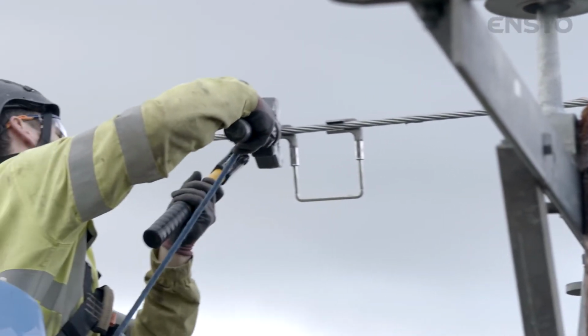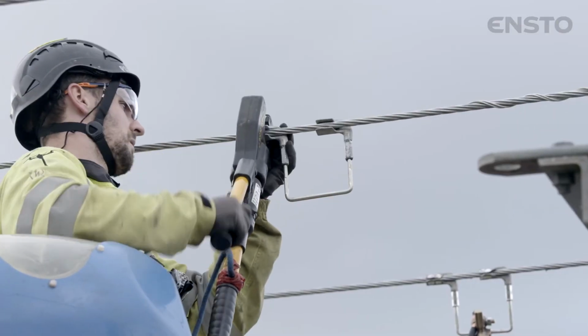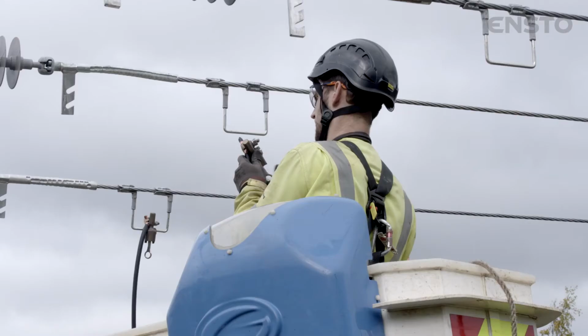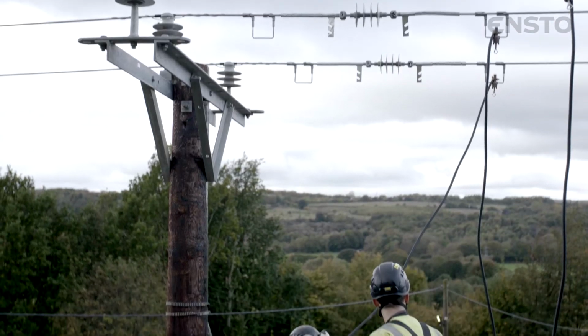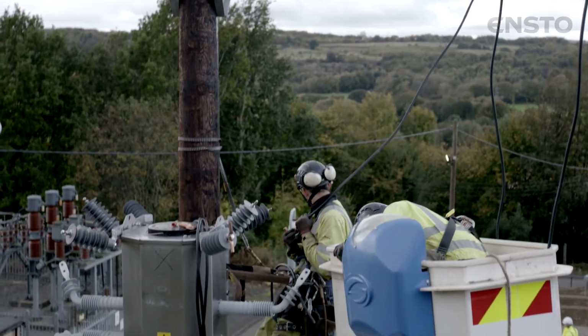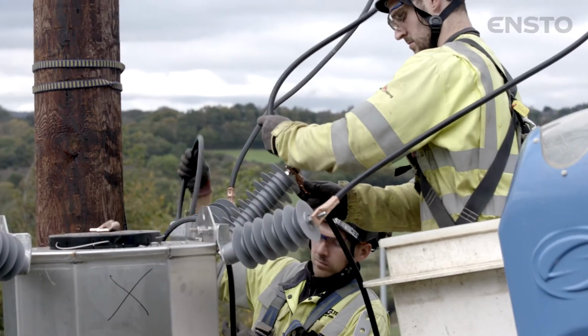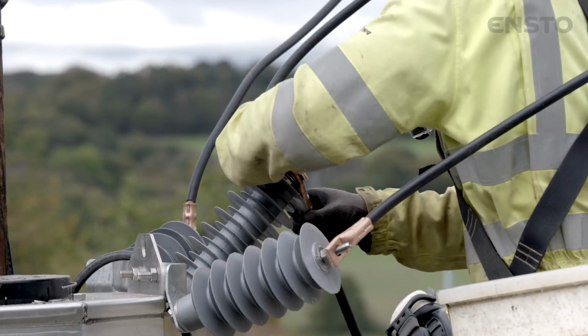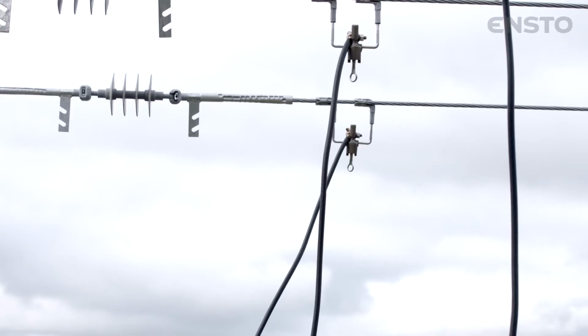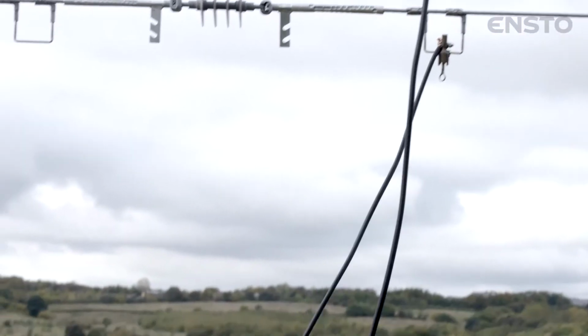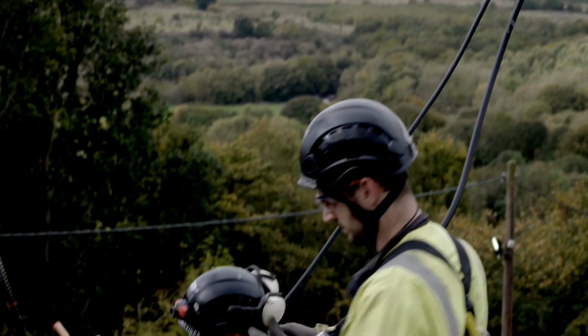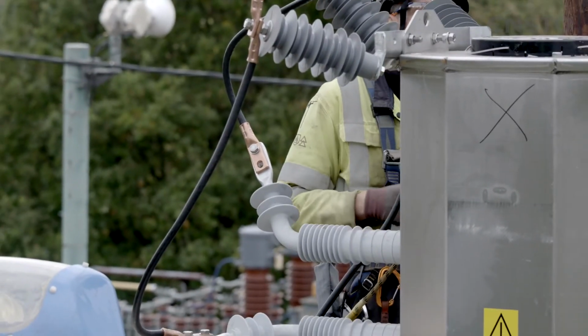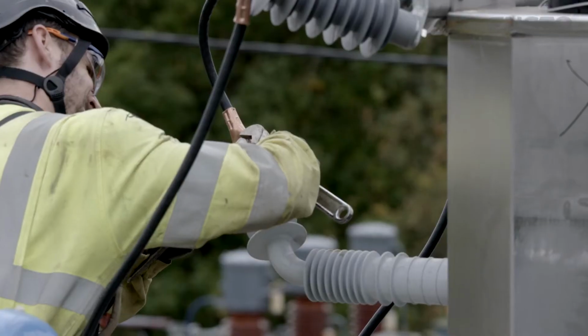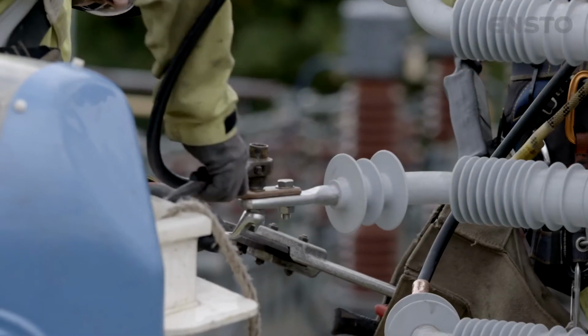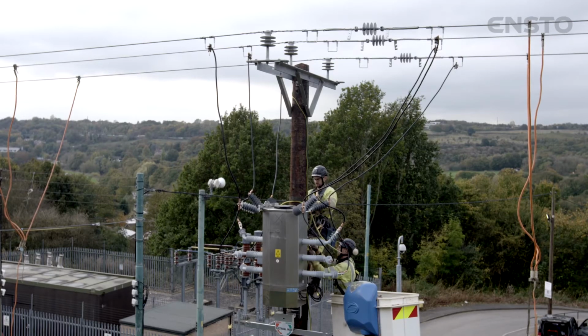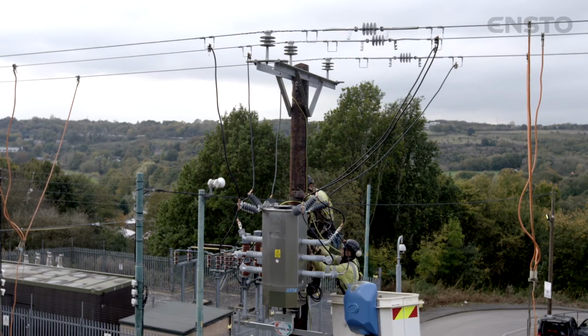Begin by crimping the bail clamps to the existing overhead line, either side of switch, 6 in total. Measure and make up 6 jumpers, crimp lugs, and bolt to surge arrestors. Connect the jumpers to bail clamps on the overhead line. Make up 6 short jumpers between the surge arrestors to bushings on the switch. Crimp lugs and bolt onto 2 bolt bushing terminals. The switch is now connected to the 3-phase overhead line.